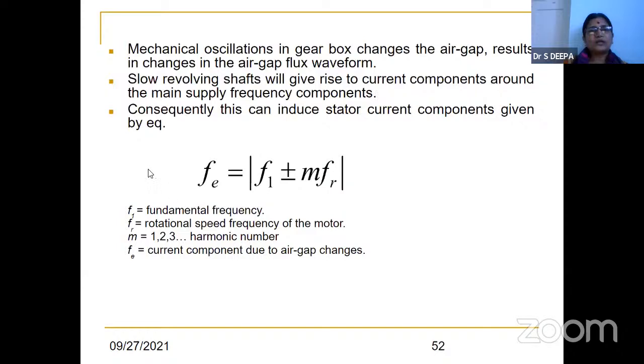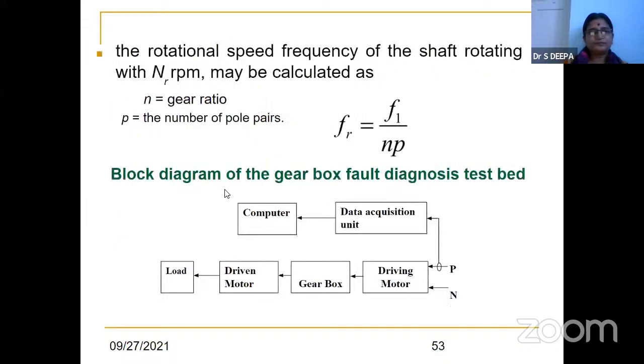So the frequencies that will come for the mechanical fault are taken up here. This is the rotational speed frequency of the shaft rotating, which may be calculated where N is the gear ratio and P is the number of pole pairs.